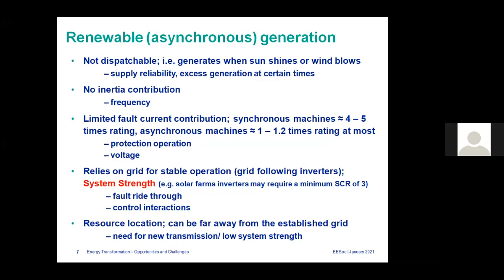So what happens is when the system strength is low, you might see fault ride-through issues, so instability of solar farms or wind farms. If there is a fault, sometimes they can't manage stable operation. They might trip or they might struggle to maintain stable operation. It's the same with interactions with other plant. We have seen that in Australia many times, in many places, where nearby solar farms and SVCs sometimes interact with each other and create oscillations, unstable or poorly damped oscillations.